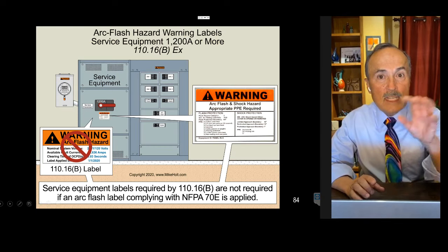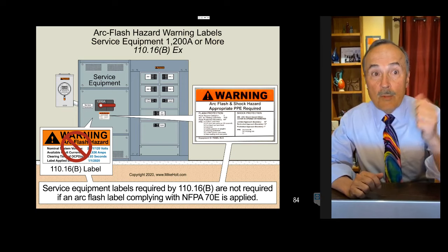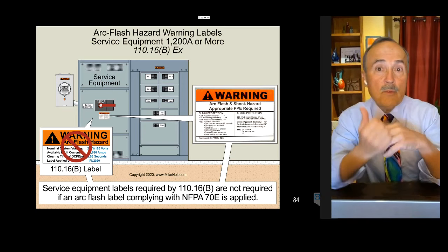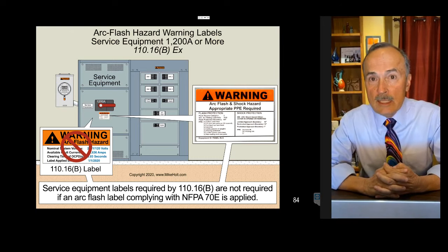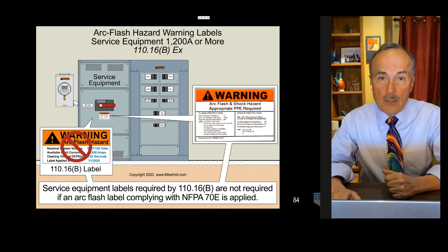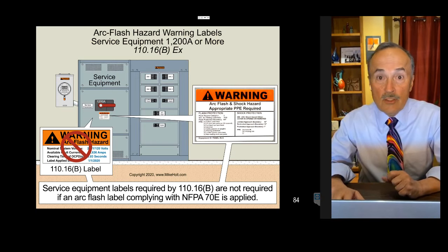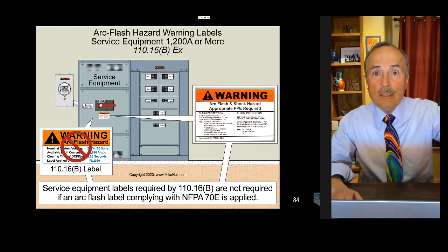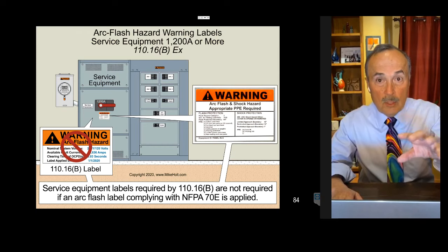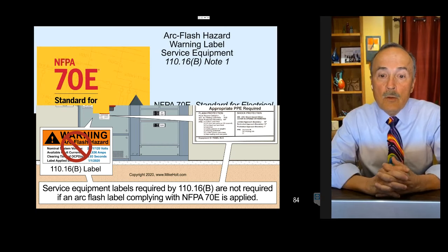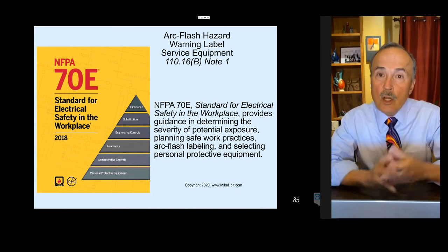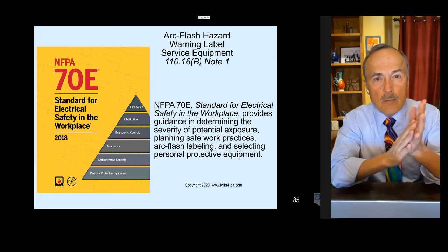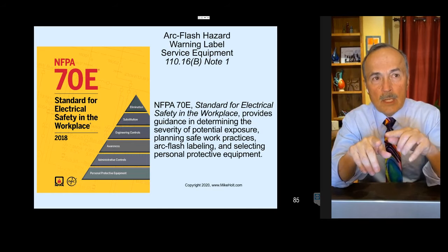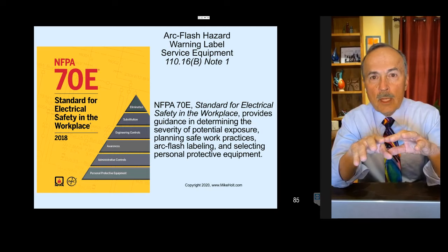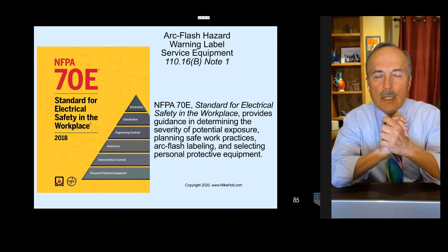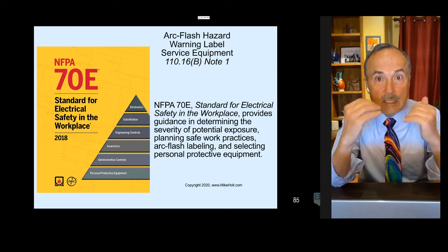110.16(B) says, you know what? You don't have to do those calculations at all. Don't worry about it. If you can go to 70E, using 70E, and you can put an arc flash shock hazard label on there that complies with 70E, well, then you don't have to worry about all those numbers. So if there's going to be an arc flash study, incident study done, and they put those labels on there, then the electrician doesn't have to worry about making that calculation. The engineer's not going to do this. He's just drawing these plans, and he doesn't know what the heck's going on after that. So in the field, you have to put, this is a field label required. All right. So 110.16(B) has a Note 1, and the Note 1 is kind of giving you the information that maybe you need to take a 70E class.